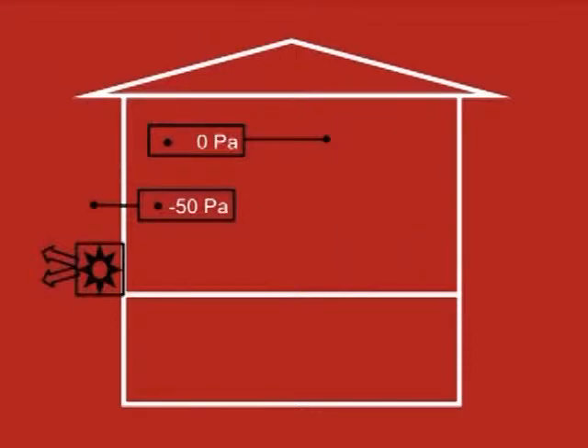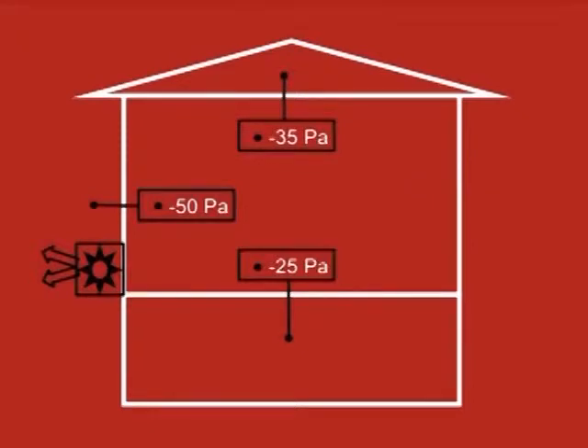Ideally, if we measure the pressure difference between two areas during a blower door test, the results will be either 0 pascals — within the same zone — or 50 pascals, if one area is inside and the other is outside the building. Unfortunately, we often measure pressure somewhere between 0 and 50. Measuring the pressure difference between two zones of a building during a blower door test is called zonal pressure analysis.